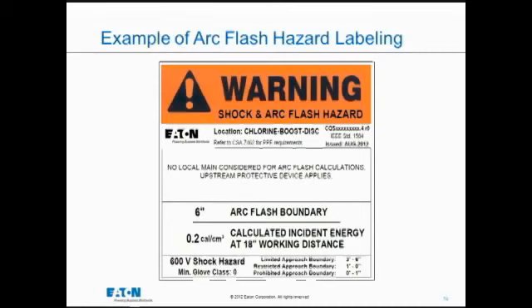Here's an example of an arc flash label. We want to warn people there's a shock and arc flash hazard. We also want to tell them, what is it? What's the quantity of the hazard? And so that is now the way that our company, Eaton, is putting together an arc flash hazard label. There is no standard to say the label must look exactly like this.